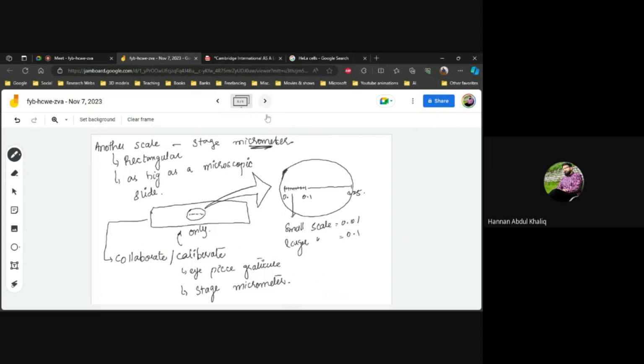Now, how is the calibration done? You have the eyepiece above. You put the eyepiece over here, 0 to 100, and you have the stage micrometer 0 to 0.25. Now, it seems that they are equal. Always remember that we magnified the things. We have adjusted them to coincide with each other. That is why they appear equal, but they are not equal.